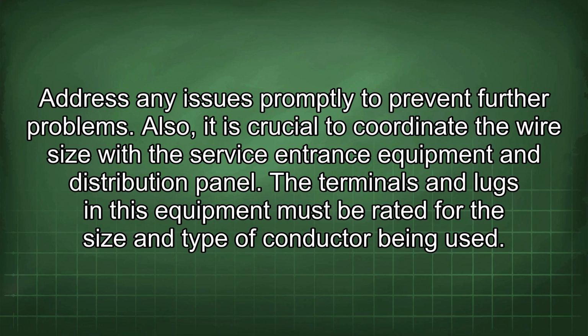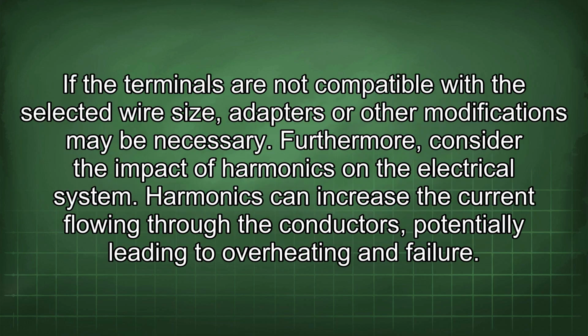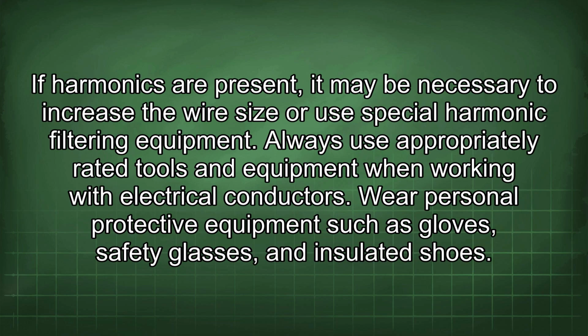Also, it is crucial to coordinate the wire size with the service entrance equipment and distribution panel. The terminals and lugs in this equipment must be rated for the size and type of conductor being used. If the terminals are not compatible with the selected wire size, adapters or other modifications may be necessary. Furthermore, consider the impact of harmonics on the electrical system. Harmonics can increase the current flowing through the conductors, potentially leading to overheating and failure. If harmonics are present, it may be necessary to increase the wire size or use special harmonic filtering equipment.